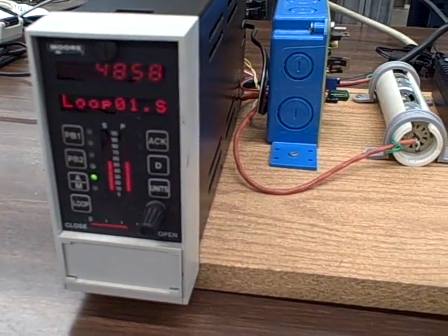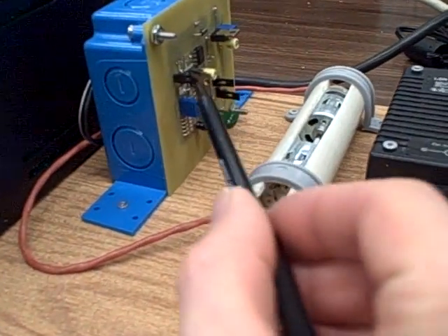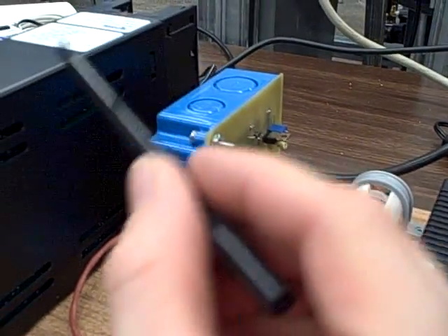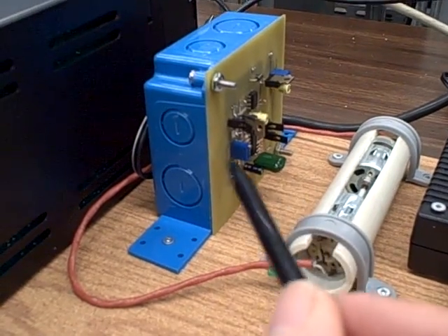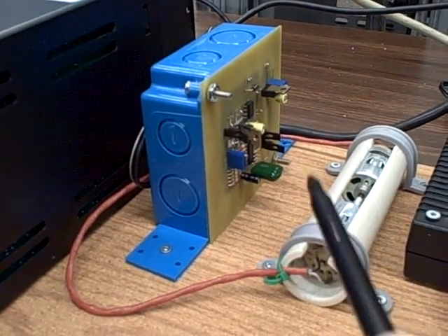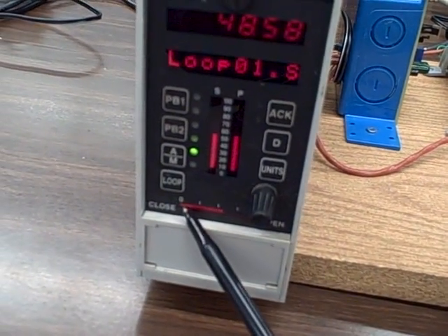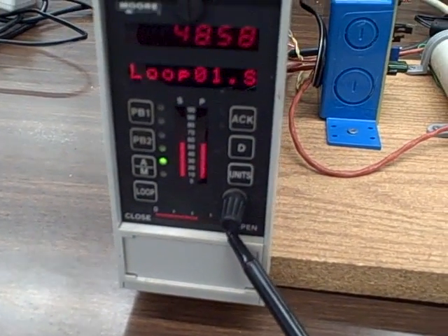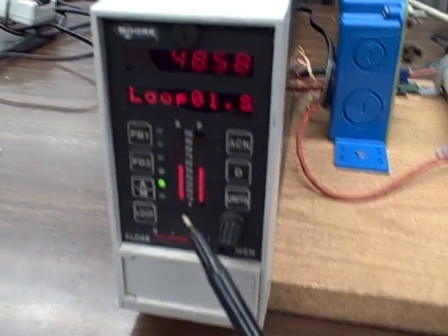Well, I'm going to throw a wrinkle into this whole loop here by changing the response of my variable speed circuit. Right now, the variable speed drive takes a 4-20 milliamp signal from the controller, uses that to throttle the electric power to the motor, and currently it's set up for direct action. That means a greater milliamp signal puts more power to the motor, which means, of course, in that mode, as the bar graph on the controller goes up and drives towards 100%, it's going to drive more power to the motor. That makes intuitive sense, but it doesn't have to be that way.